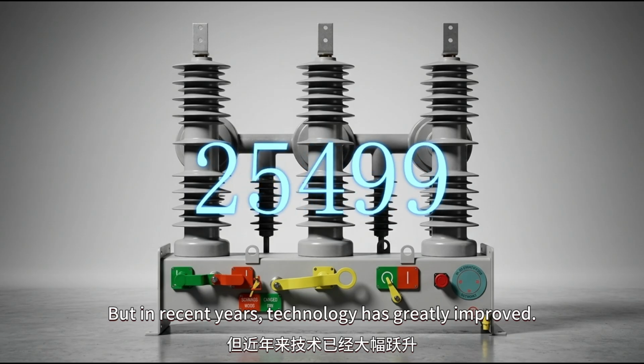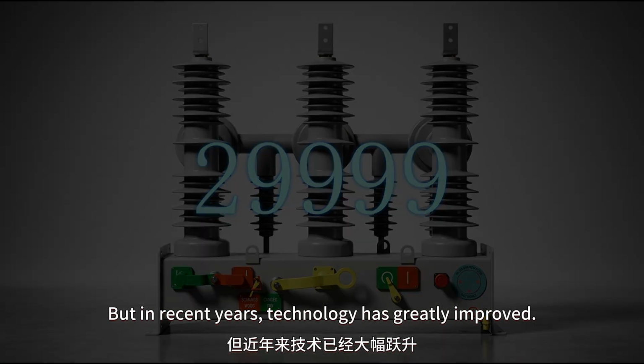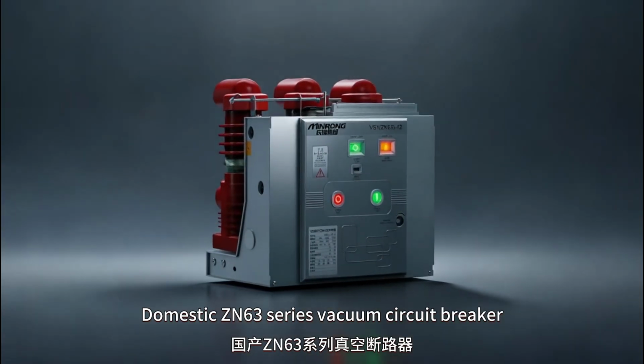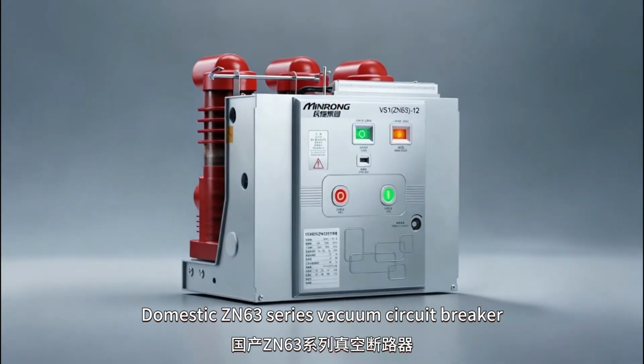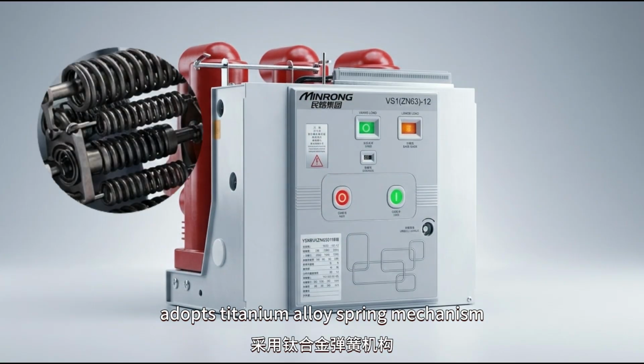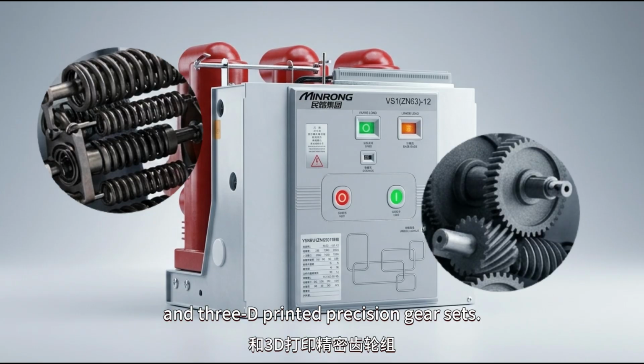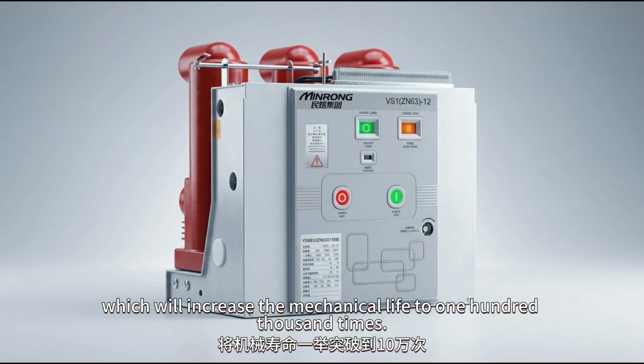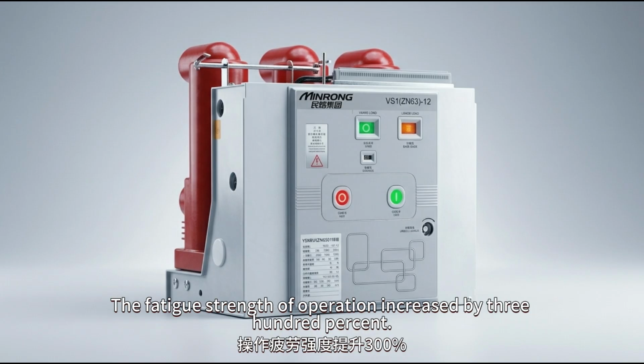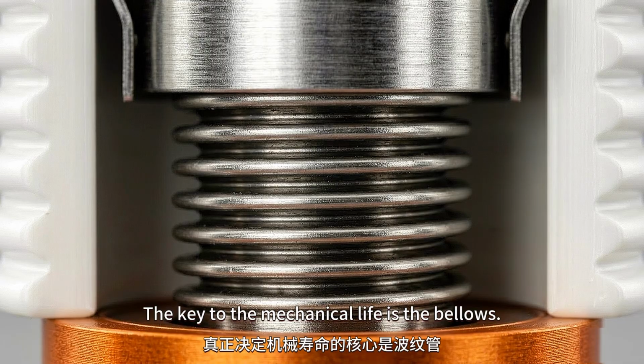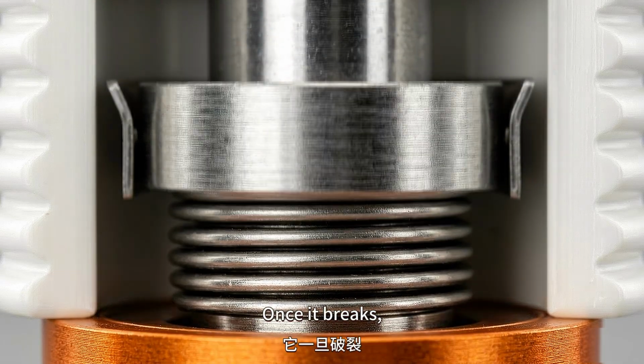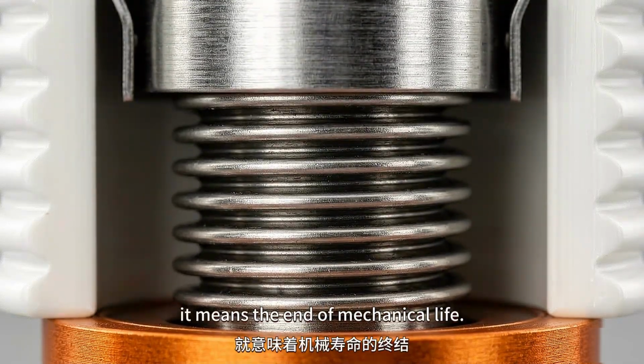But in recent years, technology has greatly improved. In 2025, the domestic ZN63 series vacuum circuit breaker adopts a titanium alloy spring mechanism and 3D printed precision gear sets, which will increase the mechanical life to 100,000 times. The fatigue strength of operation increased by 300%. The key to the mechanical life is the bellows. Once it breaks, it means the end of mechanical life.